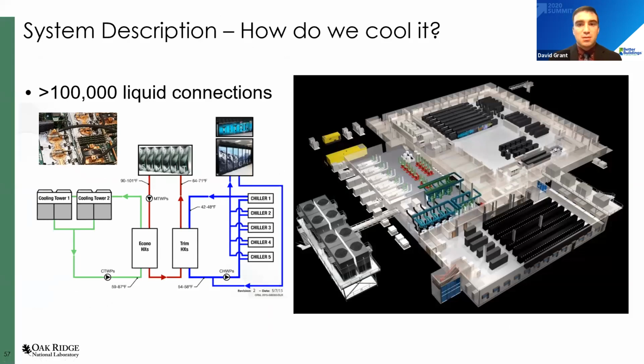And so this diagram shows the cooling system in its major components. Where you see the Summit cabinets, that represents the rear door heat exchanger and the cold plate cooling that's taking place inside of each of those nodes. And so this system was designed for a 70-degree Fahrenheit entering water temperature, and each rack needed roughly 18 gallons per minute, according to the design specifications. So water actually enters the rear door heat exchanger first and picks up the air side load from each rack, and then leaves the rear door heat exchanger and enters the rack itself into some manifolds that are inside, where the water is distributed to each of those nodes.